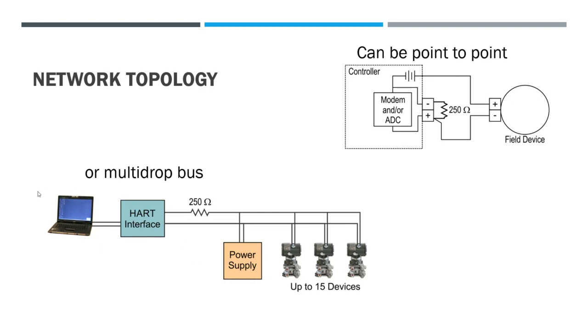This is what the HART multi-drop bus would look like. Again, it has a major bus, and then drops that come off of the bus itself. For HART, we can run up to about 15 devices. And you remember in third year, we said you can run 15 devices, but typically you're limited by the size of the power supply.